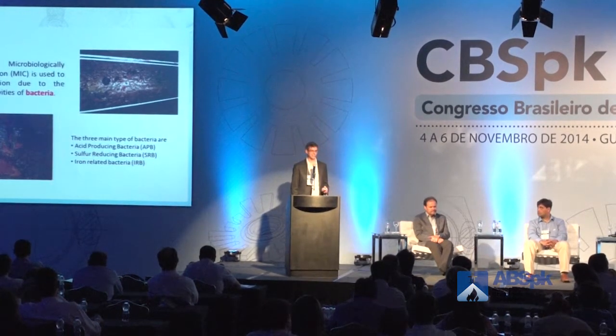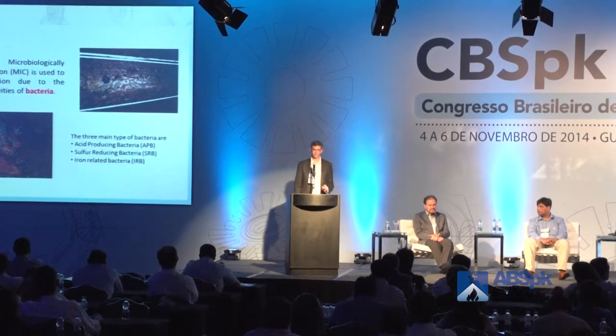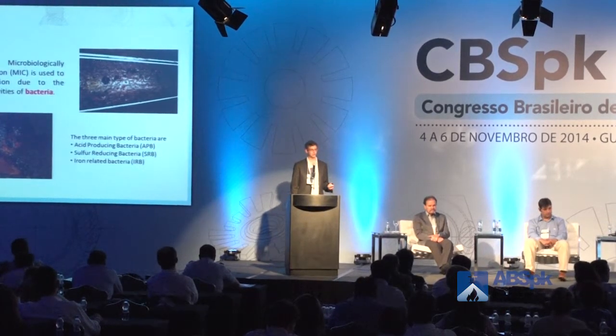If you have all three of those in your sprinkler system, you're going to have corrosion happening. Microbiologically influenced corrosion is actually corrosion caused by bacteria in the fire sprinkler system. The bacteria create corrosive conditions that lead to very fast failures in sprinkler systems. FM Global did a study on corrosion and wanted to determine what the main problem of corrosion was in fire sprinkler systems. What they found was 60% of sprinkler systems have corrosion failures due to just generalized corrosion, which is water, iron, and oxygen. 40% were related to the bacteria in the system.